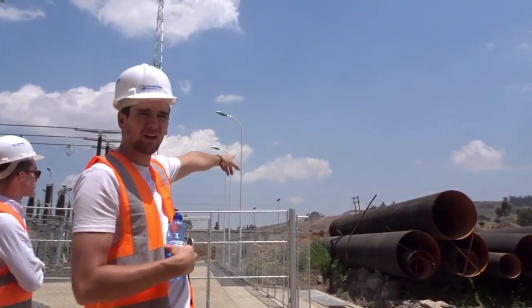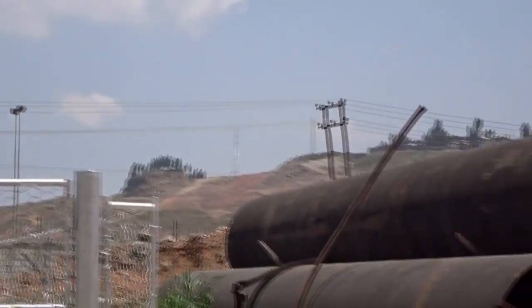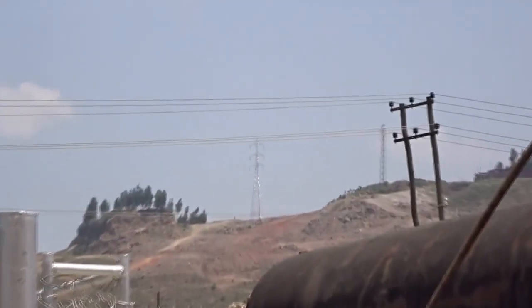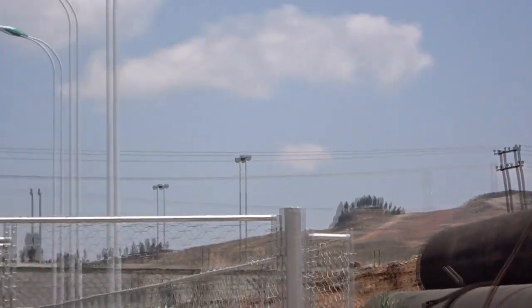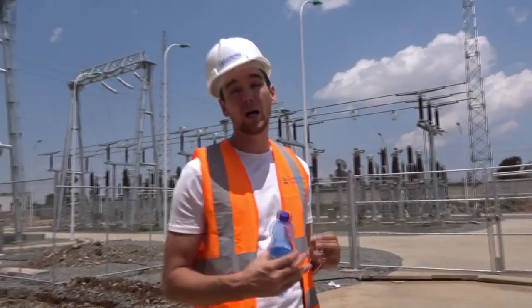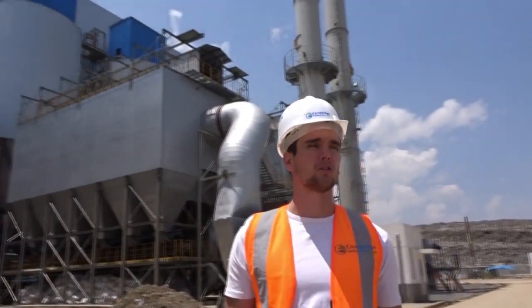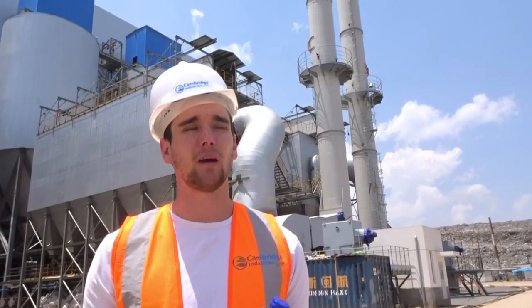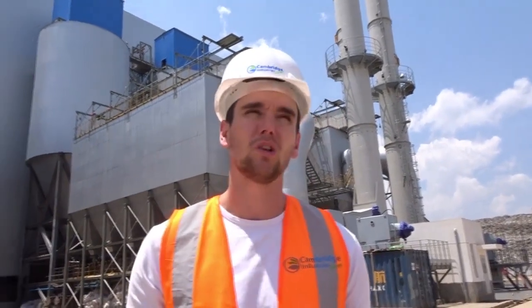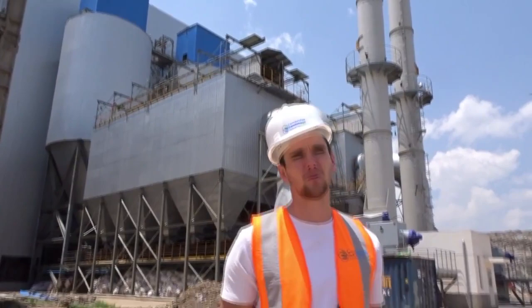There's a shiny tower on top of the hill — that's our transmission line. It's only 3.2 kilometers from the facility to the main grid, which is an extremely short distance compared to hydropower or wind power. That's good economically, and also because energy loss in transmission lines is very high in Ethiopia — around 19%. So you can actually use the energy you produce more efficiently from waste-to-energy because of the short transmission distance.